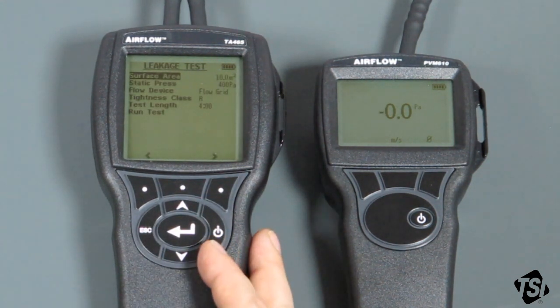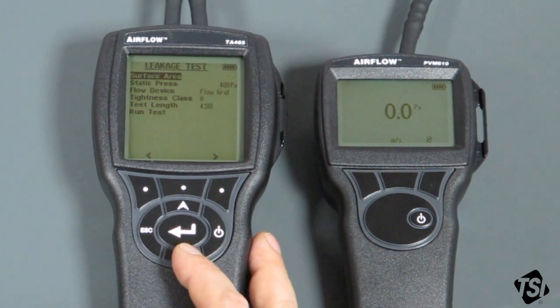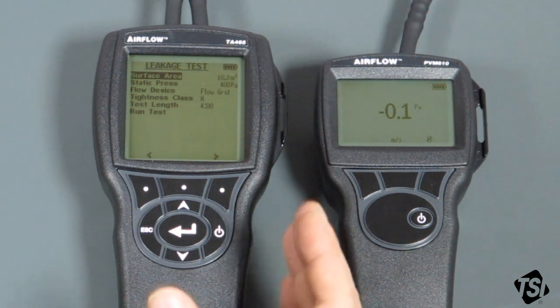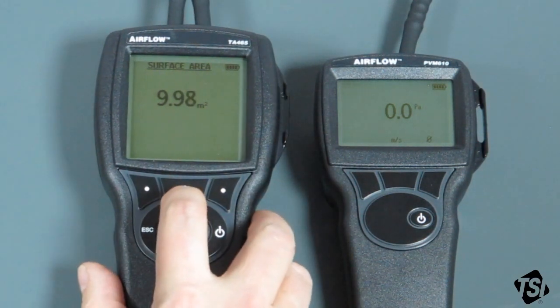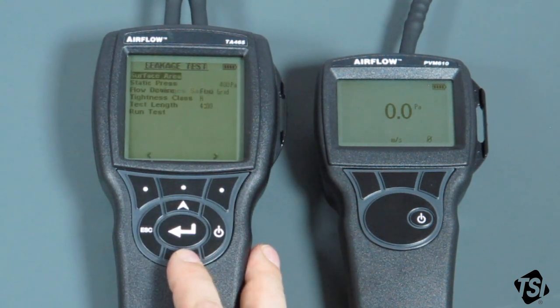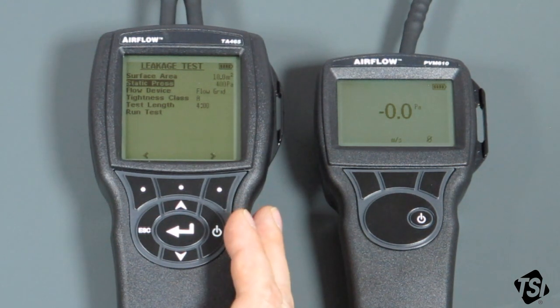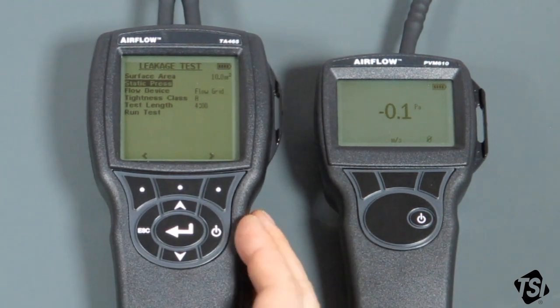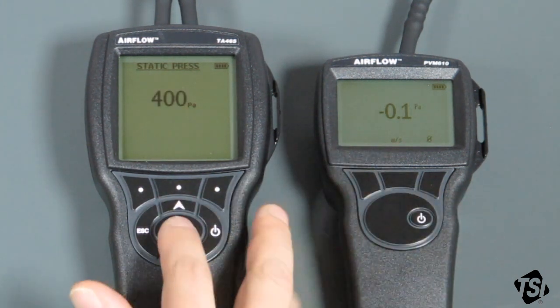We're now in the main Leakage Test menu. All the options in here need to be set up correctly, and I recommend working from the top to the bottom. The surface area is the surface area of the ductwork system you're about to test — please don't confuse this with the cross-sectional area of the duct; it is the surface area of the outside of the duct, so you need to have that value measured and ready. In this case we're going to assume 10 square metres. You can change that using the arrow keys, then press the right arrow to save that value. Moving down to the next option: static pressure. This is the pressure you're going to maintain the ductwork system at during the test; you'll monitor it on the PVM610. Most standards recommend a starting point of about 400 Pascals, but your specifier should give you a value to use. We're assuming 400 Pascals — use the arrow keys to change it, then press Return when happy.